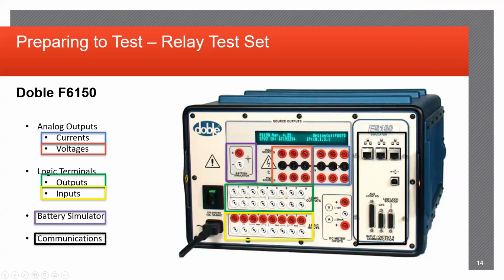So in the blue square here, you have your current outputs, and in the red square, you have your voltage outputs. Now, one tricky thing about this is when you are opening up the software, you can actually flop these ports, change them from AC current to AC voltage on one side and AC current and AC voltage to the other side. So making sure that you identify these before you start injecting any currents or voltages is extremely important as well, because you don't want to be putting currents into the voltage sections on the relay.